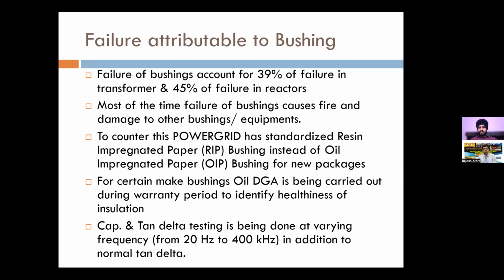Like I said earlier also, world over it is agreed that the failure rate is 1%, and most leading utilities world over are having transformer failure rate of around 0.5%. But for Power Grid it is much lower than 0.5%. Our failure rate is around 0.32%. So this is a much better record, and this we have done due to these certain measures that we have introduced.